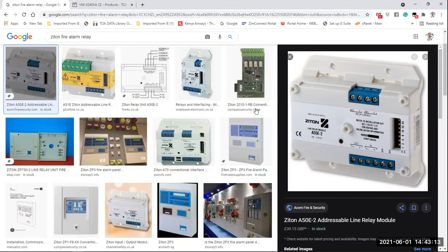Okay, let's try and clarify this. I see where the confusion is coming from. All right, cool. From the fire panel, you guys need to ask the fire panel engineers to give you 3 basic relays. 3 relays will represent, this is a single relay. This is not a dual relay. This is one relay. The next relay will be like this, another relay. The third relay will be like this, another relay.